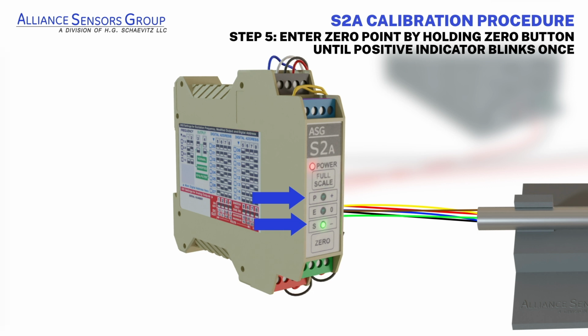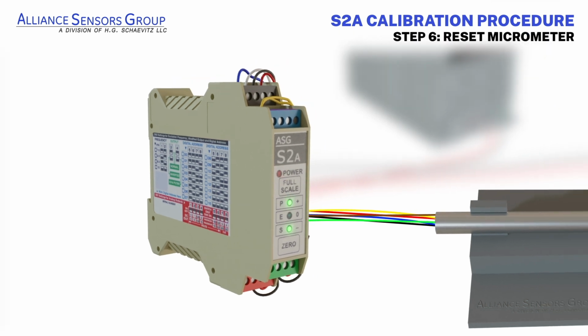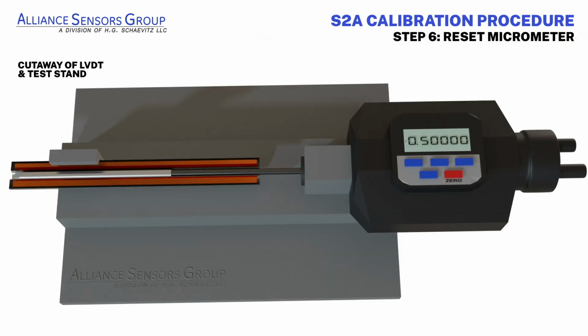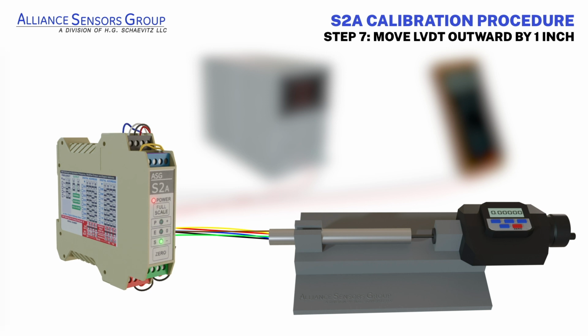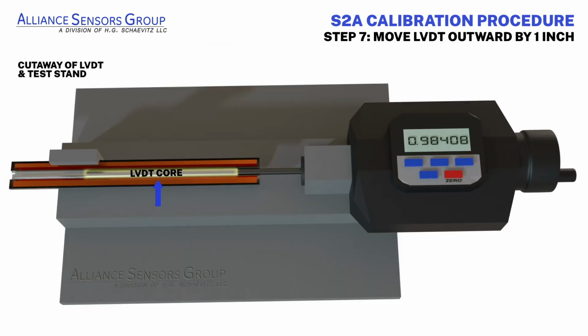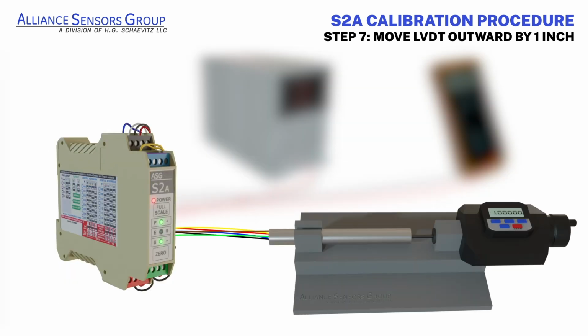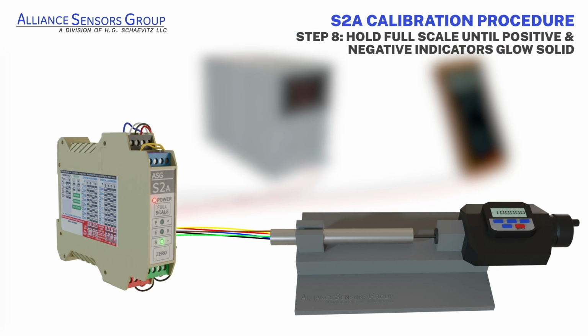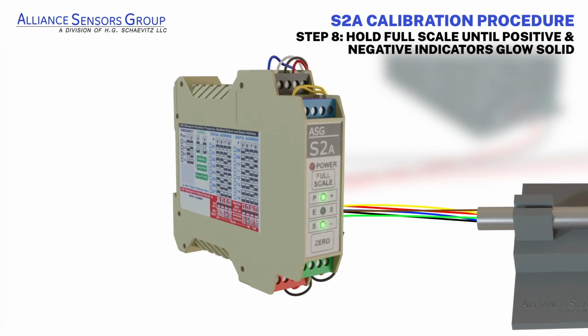Do not pay attention to the S2A's DC output while performing a calibration. Now reset the digital micrometer readout to 0. Next, we move the LVDT's core outward by 1 inch. This will take us to the positive end or 1 inch position of the LVDT core's stroke and will be the S2A's 10 volts DC full scale output position. When that position has been reached, momentarily hold the full scale button down until both the positive and negative indicators illuminate solid. This indicates that the system calibration has been successfully completed.